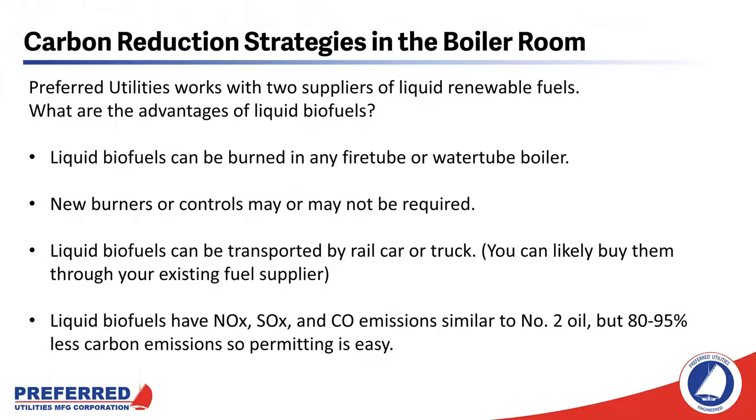Preferred Utilities works with two suppliers of liquid renewable fuels. The advantages of liquid renewable fuels include they can be burned in any fire tube or water tube boiler — they can be burned in your existing boilers. New burners or controls may or may not be required depending on what you have existing. Liquid biofuels can be transported by rail car or truck, and you can likely buy them through your existing fuel supplier. Liquid biofuels have NOx, SOx, and CO emissions similar to number two oil, but 80 to 95 percent less carbon emissions, so air permitting should be an easy process.